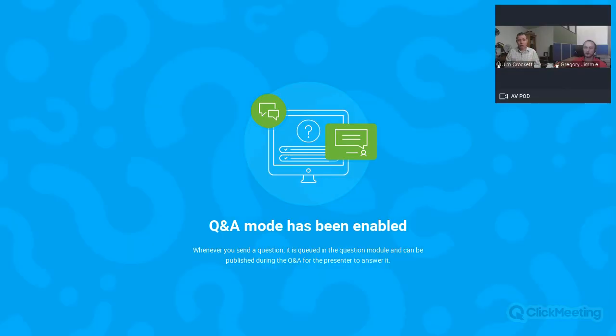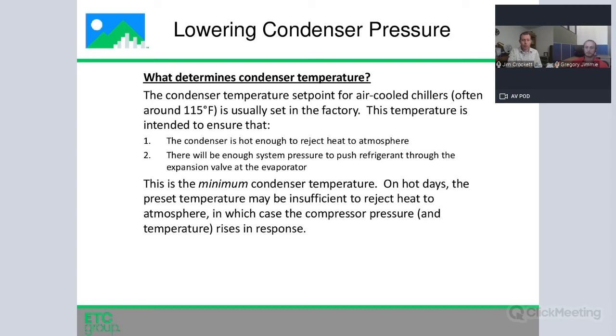So even if it's set for 115, if the refrigerant in the condenser is not hot enough for the energy to be carried away to atmosphere, the fans back down and the condenser gets hotter. The condenser will automatically get hot enough to carry the heat away. Now, what that means is that you'd be able to get away with setting it lower. If you could set it for 95 instead of 115, most days that would still be hot enough to reject your heat to atmosphere. And if you did have a 105 degree day, the condenser temperature and pressure would automatically rise in response. So that's one way to lower your condenser pressure, is to lower the condenser pressure set point.